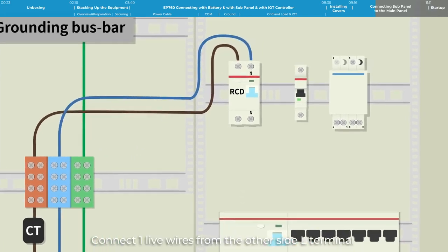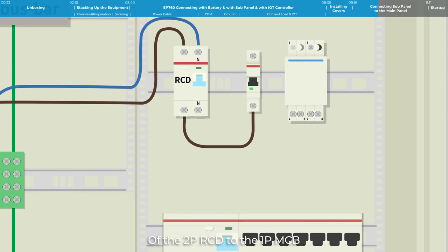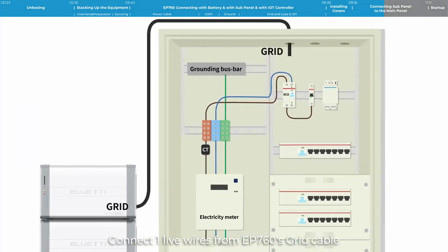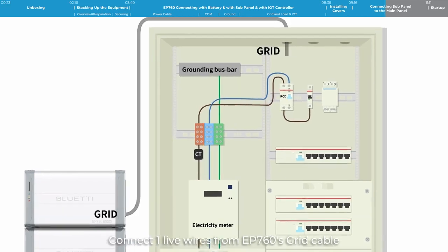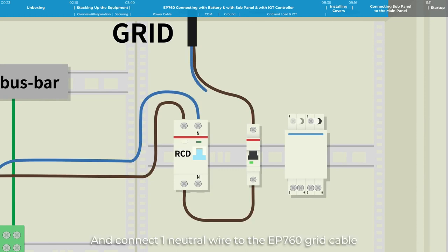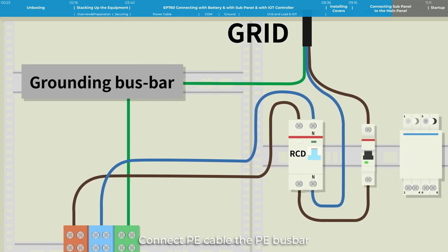Connect one live wire from the other side L terminal of the 2P RCD to the 1P MCB, miniature circuit breaker terminal. The sequence from left to right is L N. Connect one live wire from EP760's grid cable to the other side of the 1P MCB, and connect one neutral wire to the EP760 grid cable. Connect PE cable to the PE bus bar.